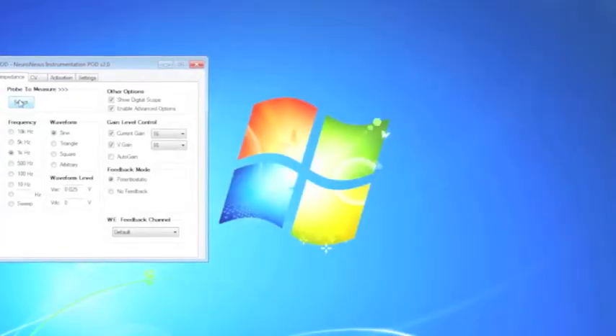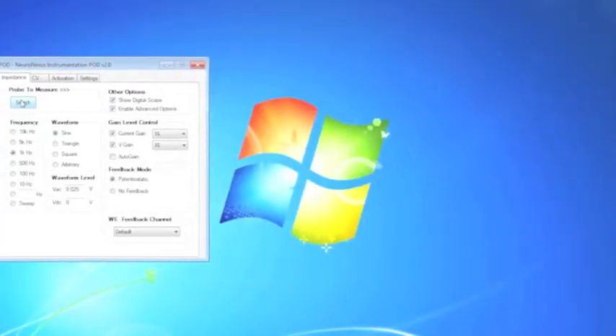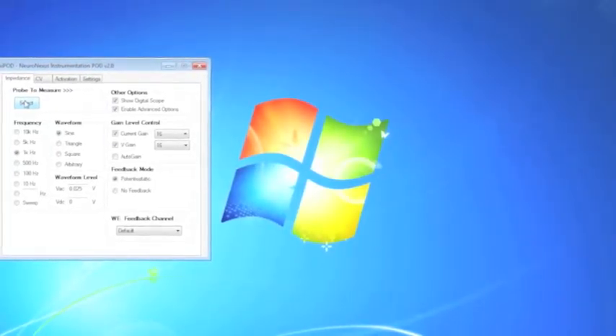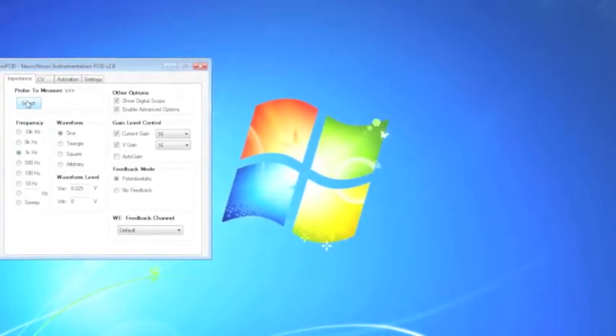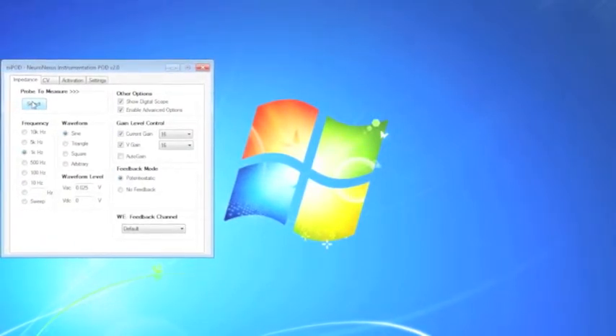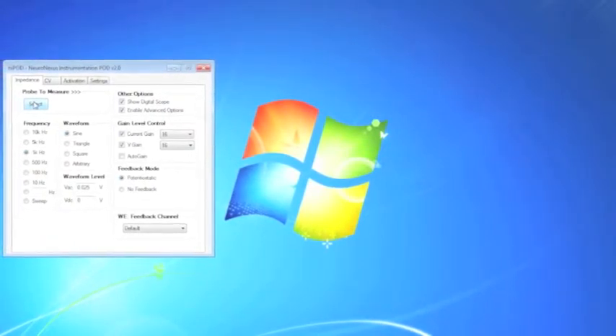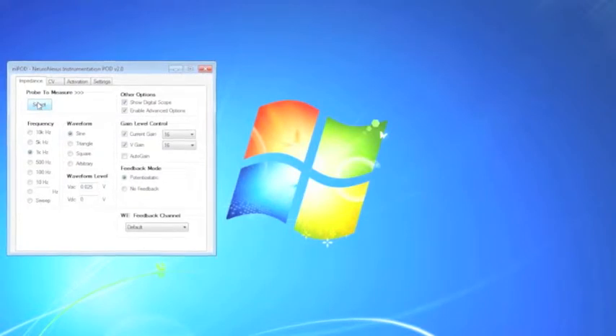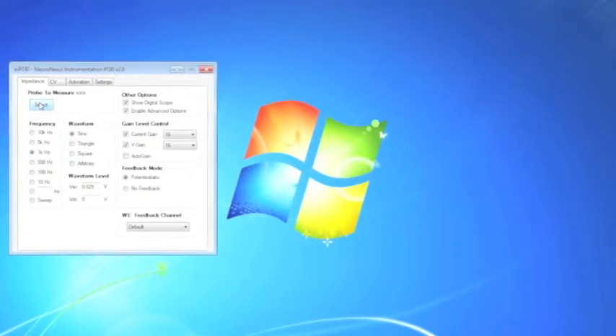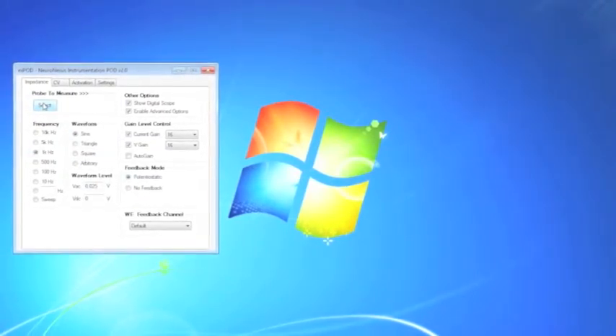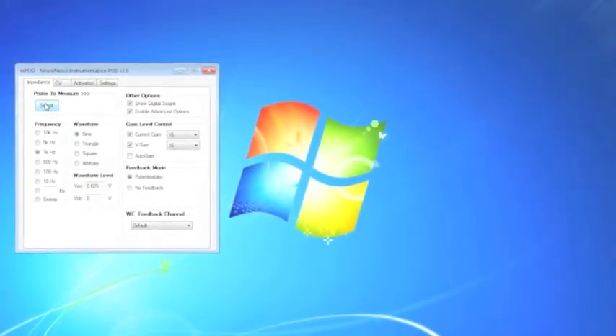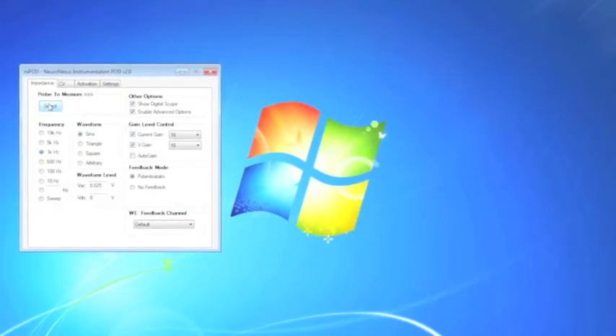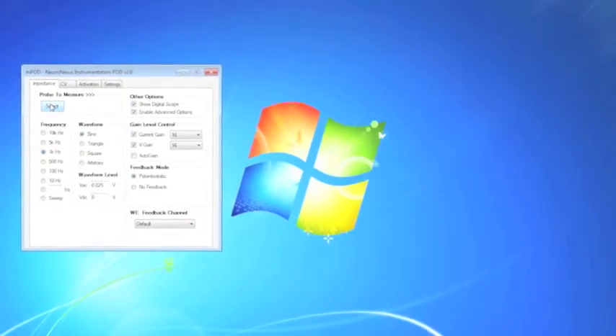From the main interface, you can change frequency, waveform, and gain settings. By default, the measurement is done applying a 1K sine wave. For advanced operations, you can change the waveform settings or run a frequency sweep. For day-to-day measurements, it is not necessary to change the settings here.